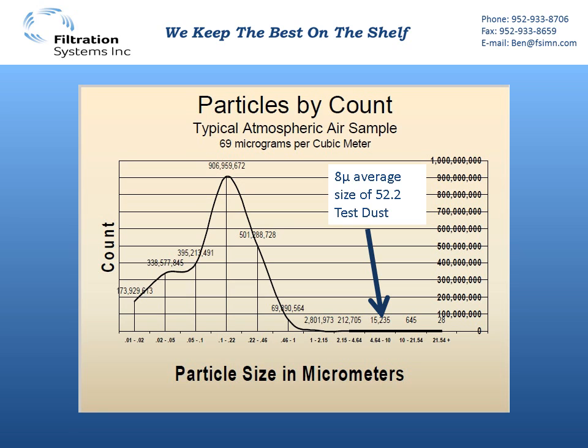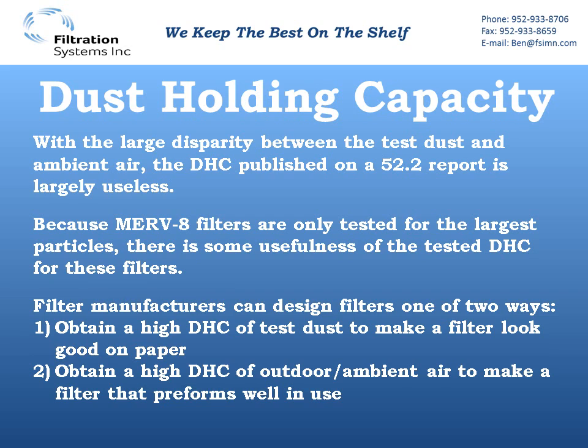This is another way of graphically looking at the distribution of particles in the air and where the ASHRAE test dust fits within that distribution. Because of the large disparity between the size of the ASHRAE test dust and the size of dust in ambient air, dust holding capacity published on a 52.2 report is pretty much useless.